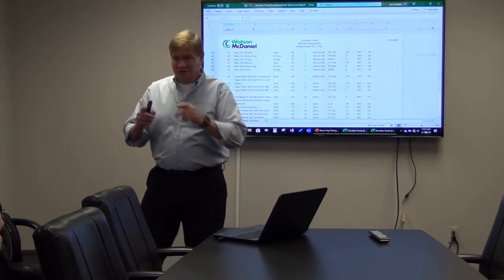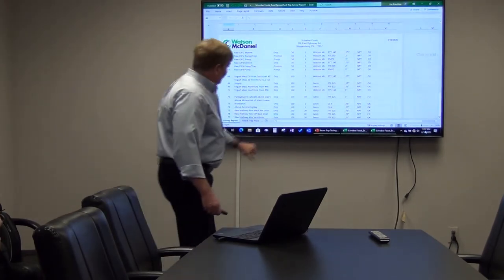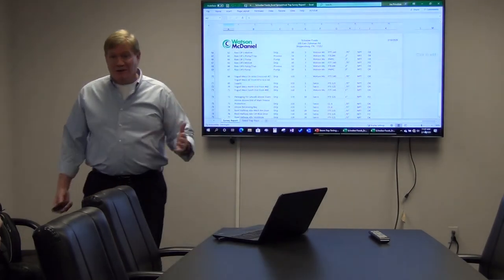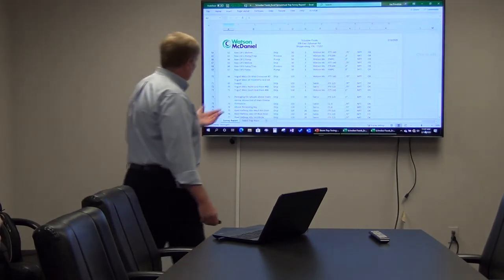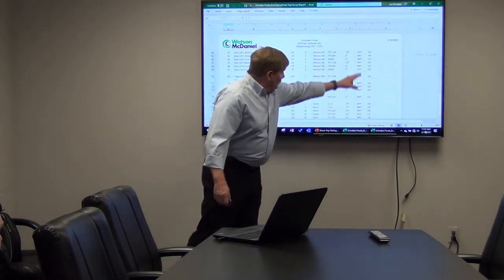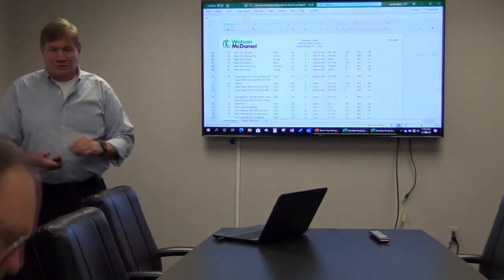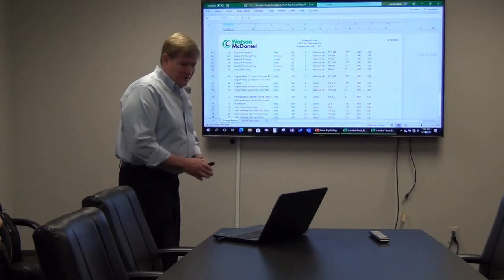The I designates an inline, meaning the pipe goes straight through, and this is the operating pressure, 125 PSI. So now I can go to our crossover guide and say, oh, it's an FTT dash. In our case, we'd use a 145 with a 3/4 inch. And again, we're recording all this, so when the outside guys come with us, somebody stands there with a little clipboard putting all this information down.